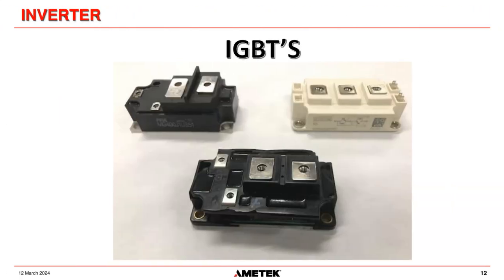And here is what power inverter modules look like. They're quite sizable. They're about the size of a man's wallet for the IGBTs that we use inside our UPS systems. And there's obviously various different versions. This one here is a single IGBT. So one of these will be the collector. This will be the emitter. And then we have our gate emitter signals going into these terminals here.